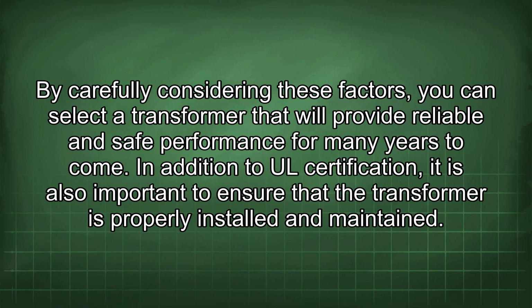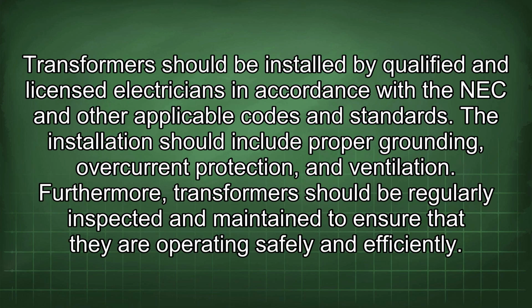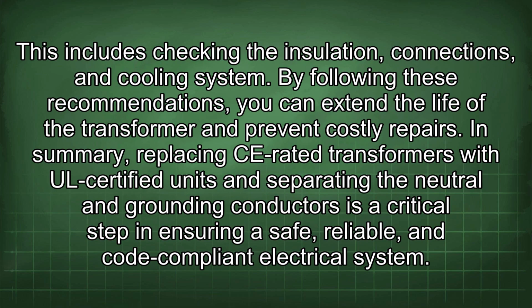In addition to UL certification, it is also important to ensure that the transformer is properly installed and maintained. Transformers should be installed by qualified and licensed electricians in accordance with the NEC and other applicable codes and standards. The installation should include proper grounding, overcurrent protection, and ventilation. Furthermore, transformers should be regularly inspected and maintained to ensure that they are operating safely and efficiently. This includes checking the insulation, connections, and cooling system. By following these recommendations, you can extend the life of the transformer and prevent costly repairs.